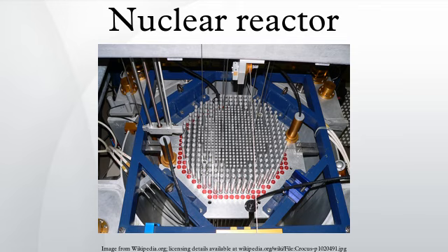Thermal neutrons have a far higher cross-section of fissioning the fissile nuclei uranium-235, plutonium-239, and plutonium-241, and a relatively lower probability of neutron capture by uranium-238 compared to the faster neutrons that originally result from fission, allowing use of low-enriched uranium or even natural uranium fuel. The moderator is often also the coolant, usually water under high pressure to increase the boiling point.